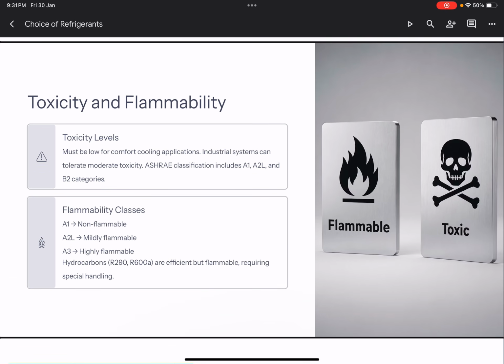A third and the most important chemical property is the flammability. If the refrigerants are flammable, then they are not recommended for domestic applications. Generally, the categorization is in terms of A1, A2, and A3, where A1 is considered very safe, non-flammable, whereas A3 is considered not at all safe, meaning highly flammable. Hydrocarbons are efficient thermodynamically, but they are A3 types of refrigerants, meaning they have a high flammability, and hence we need careful, special handling of these refrigerants. Safety is a concern.